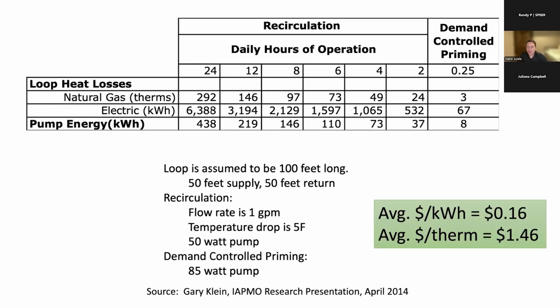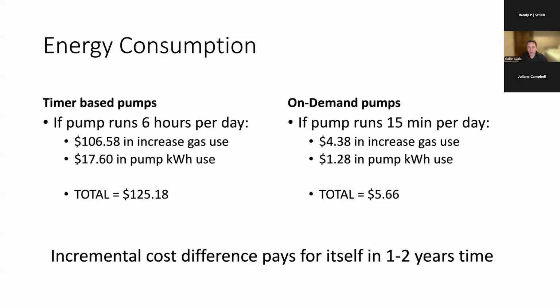There's been a lot of research that's been done on the energy cost of recirculation systems, and here we see some data from Gary Klein, IAPMO research presentation. This was some years ago, but they did some modeling, made some assumptions, and essentially showed the amount of heat losses with a timer-based pump or a 24/7 pump versus an on-demand system. And there's a significant decrease in the amount of energy and utility costs associated with these two types of systems.